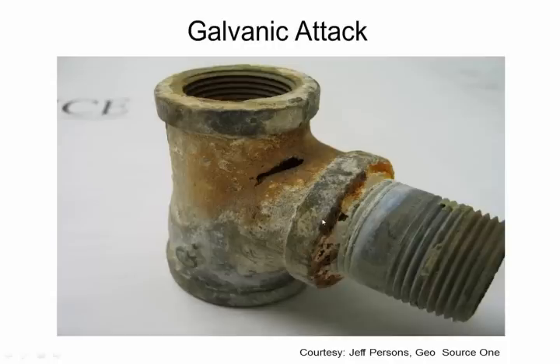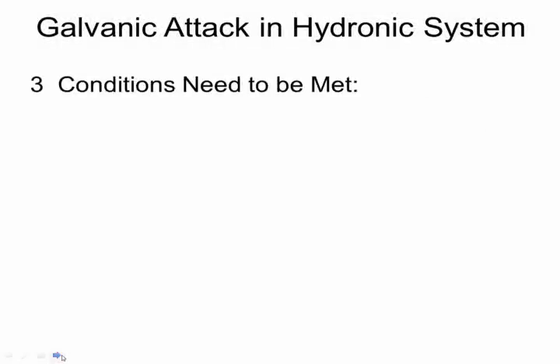It's a galvanized T with a brass nipple. The brass nipple is more noble than the less noble galvanized T, and as a result, because the system had the effects of galvanic attack that it could set up, the sacrificial lamb became this T before it outright failed. So what do you need for galvanic attack to be an issue with the system?